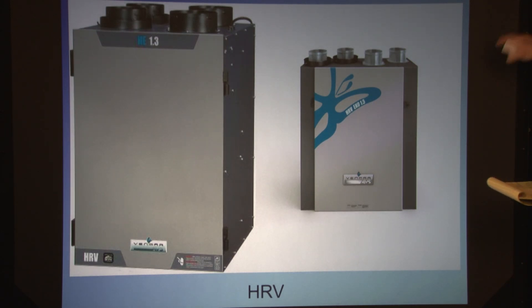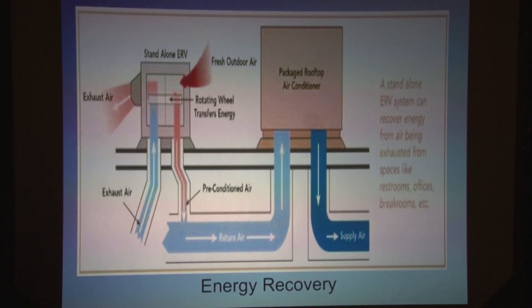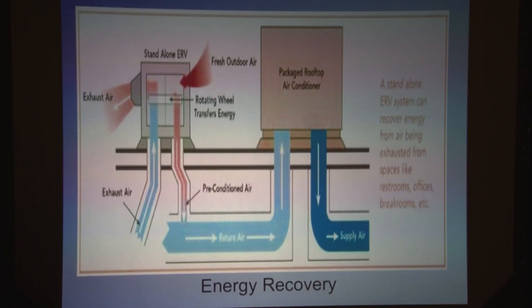Here are a couple pictures of HRVs from different manufacturers — you can see the vents for incoming and outgoing air bringing it through the core. Along with HRVs, we have energy recovery ventilators, or ERVs. This diagram shows how ERVs bring in outside air that is filtered, cooled, and dehumidified. The difference between the two is that the stale outgoing air cools the incoming air through the core, similar to how HRVs heat it. Much like an HRV, ERV air passes through an energy recovery core, and the ERV then distributes cooled, dehumidified air throughout the ductwork.